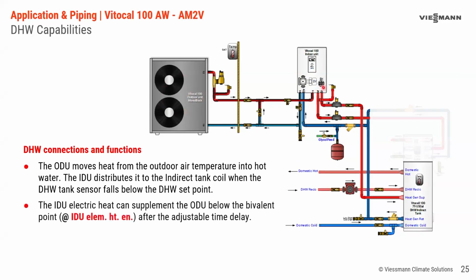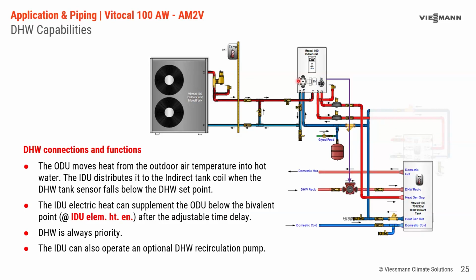And in some cases here, we might be able to augment it with the electric heat at a set point we call IDU element heating enable. And that is in the control under the heat pump group. Above that set point, whatever point we pick here, then the electric heat isn't involved. The outdoor unit is 100% responsible for it. Below this set point, we can also add the electric heat after the time delay that's built in the unit. And DHW in this system is always priority. Your DHW will always be priority in every application. And of course, the indoor unit then also has the ability to run the domestic hot water recirculation pump if that's installed in the system, and you can put a schedule on it if you want to do that. It's part of the control logic.